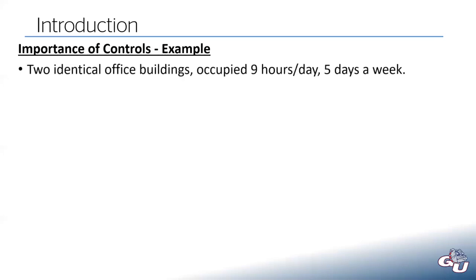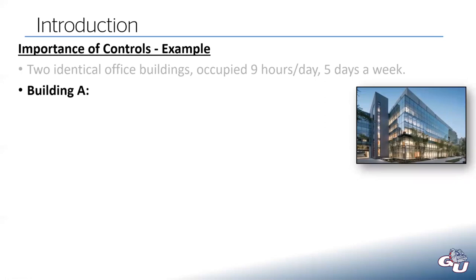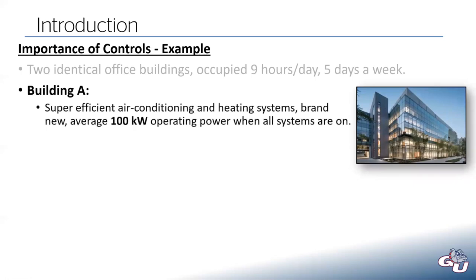I mentioned the importance of controls and that an efficient system could be operated very inefficiently. So let's say we have two identical office buildings. They're each occupied 9 hours a day, 5 days a week, a basic Monday through Friday office schedule. And let's say in building A, you've got these state-of-the-art, super efficient air conditioning and heating systems. Everything's brand spanking new, and on average, all of those systems draw about 100 kilowatts of operating power when all those systems are on.